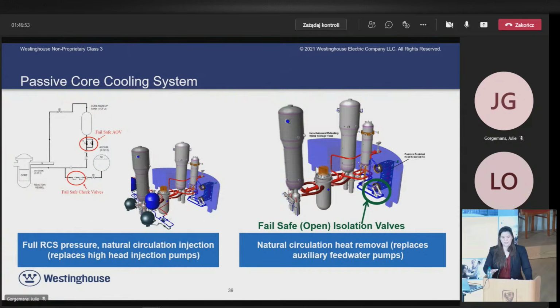In a conventional active pressurized water reactor, we have a number of pumps that are required to deliver that function. In AP1000, we actually have two tanks called core makeup tanks. They're the tanks in blue in this picture. And we're going to drain them through natural circulation. They have an inlet line which is connected to the primary loop, and that inlet line is thermally insulated. So basically it remains hot because the primary system is hot and it's connected to the primary system. And it's insulated from its environment so that it doesn't dissipate the heat that is inside. That's why in the picture, it's designed in red.